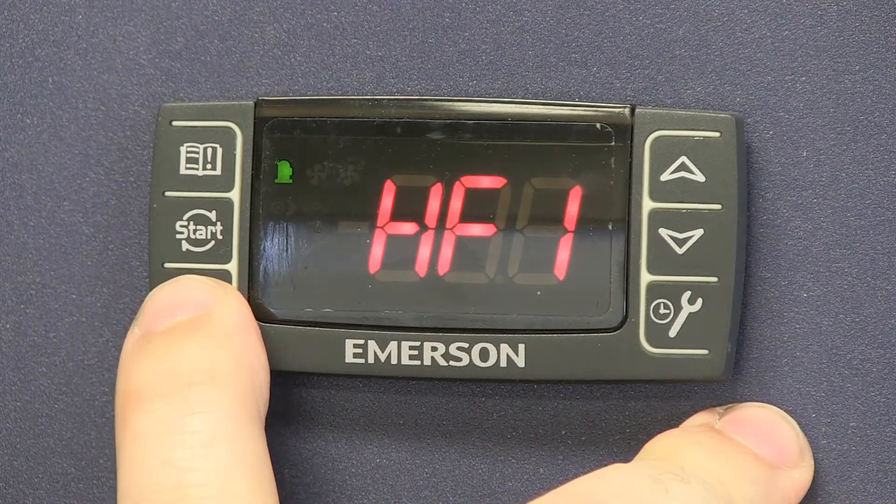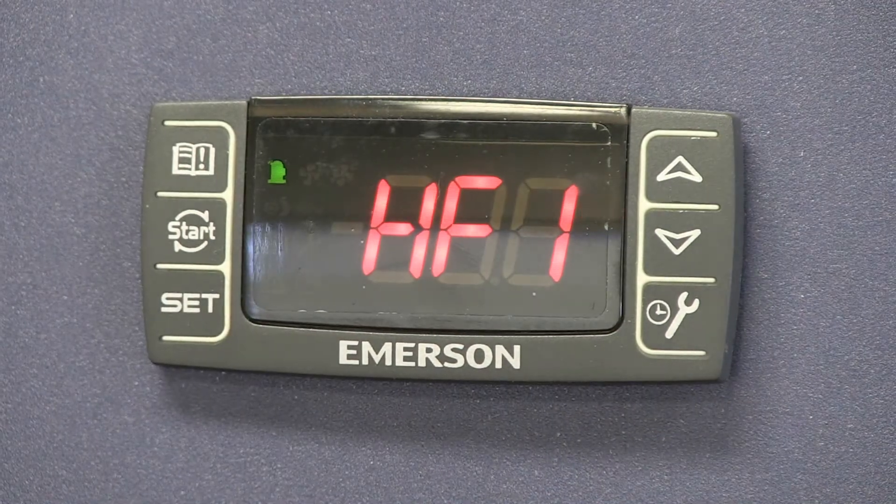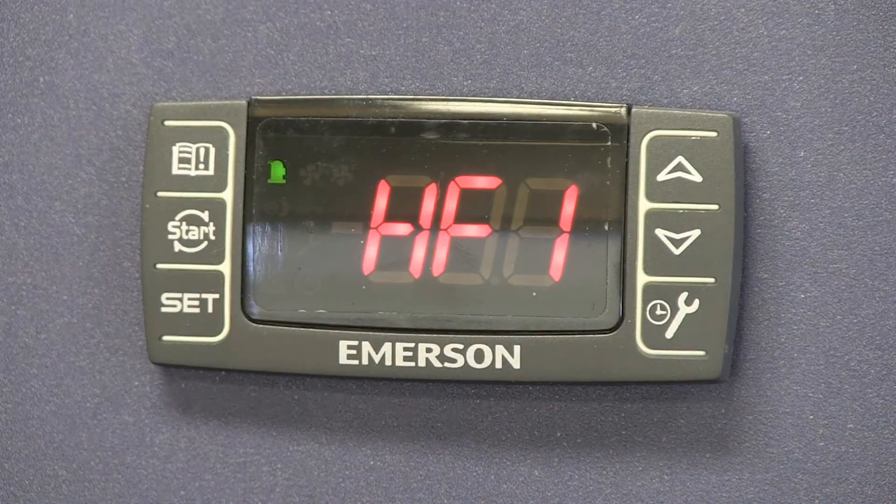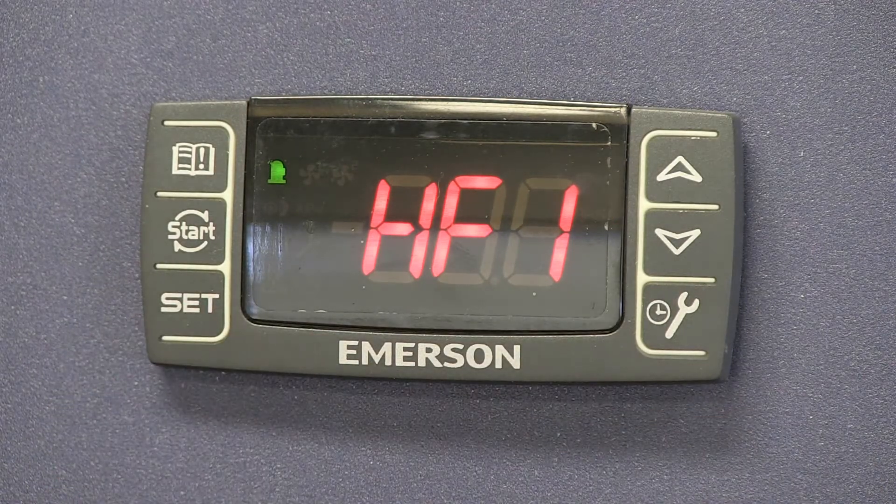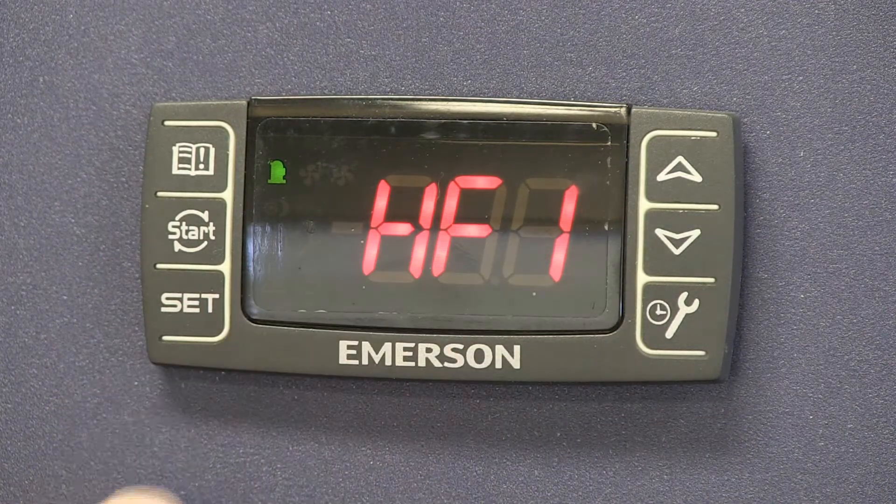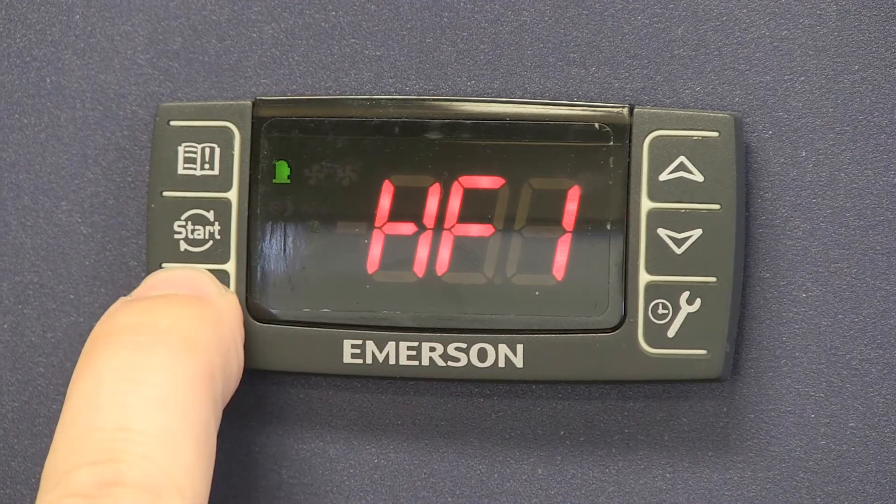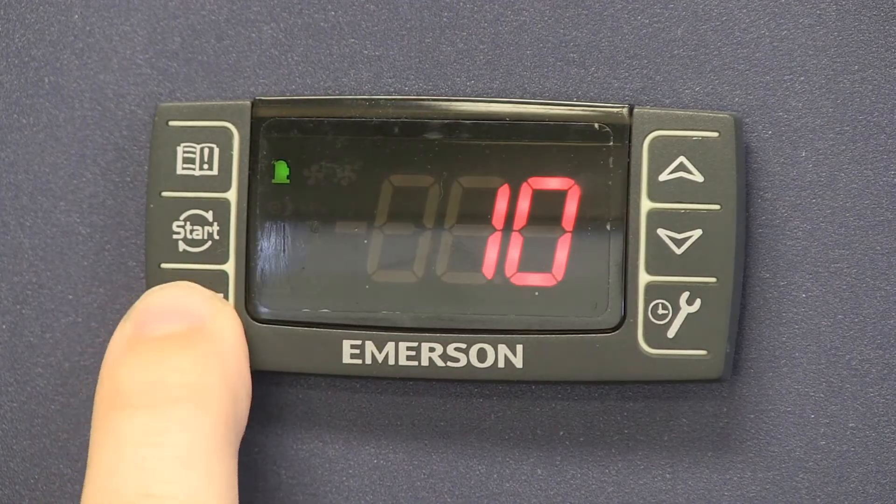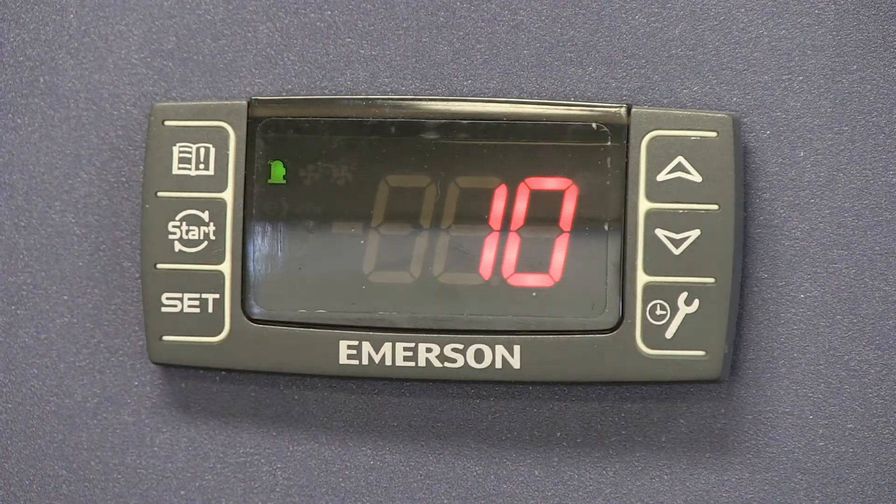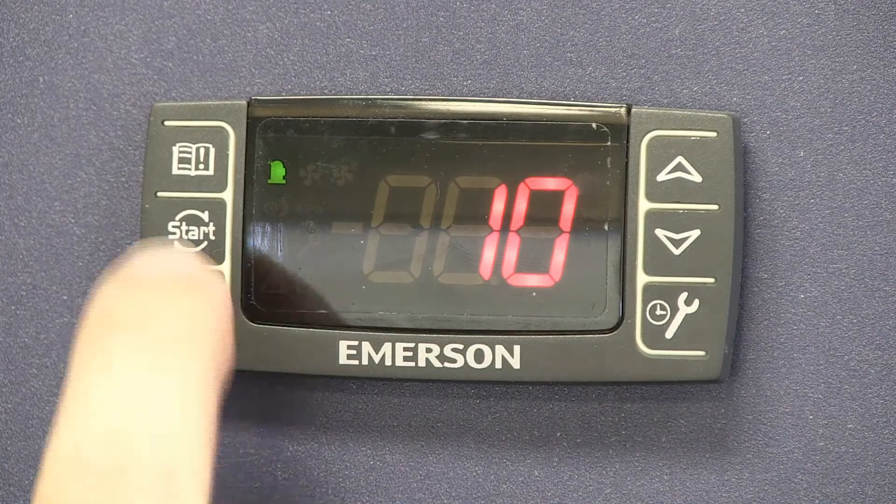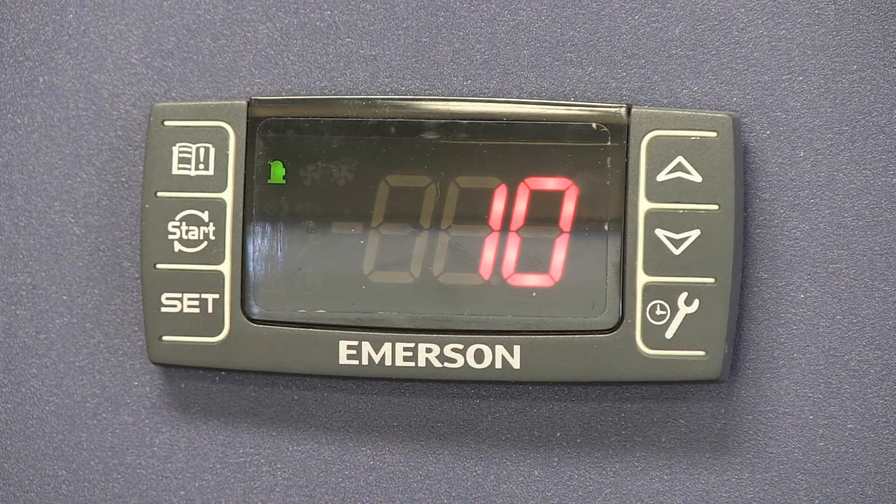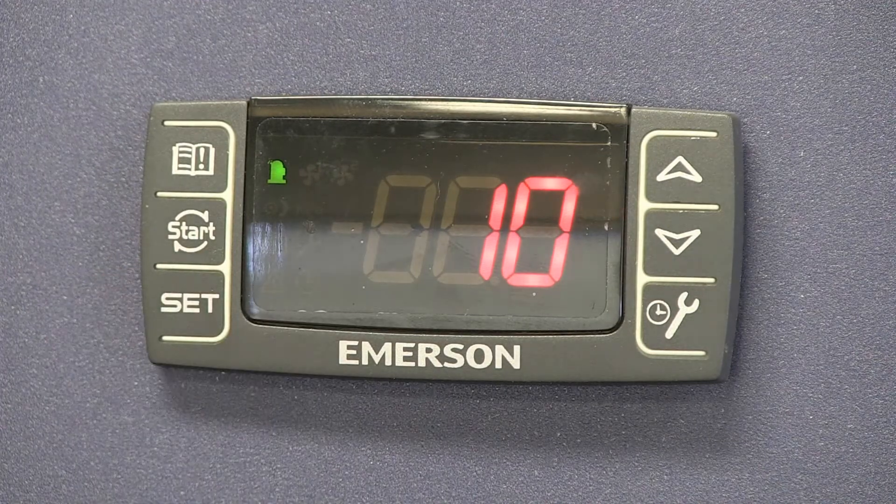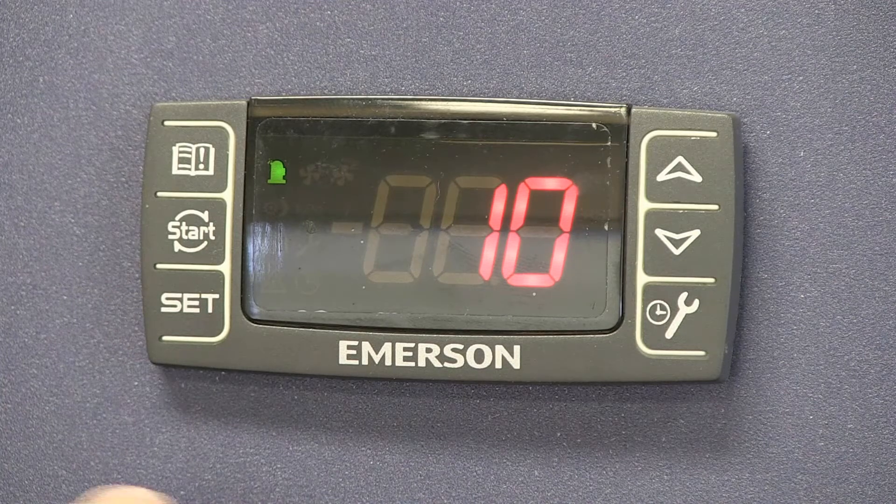And then HF1 is the differential. So this would be actually the cut in. It'd be the SF1 value plus whatever you set as the HF1 value would be your cut in. Right now it's set at 10 degrees. So that means the 80 degree cutout plus 10 degrees of this value gives you a 90 degree cut in.